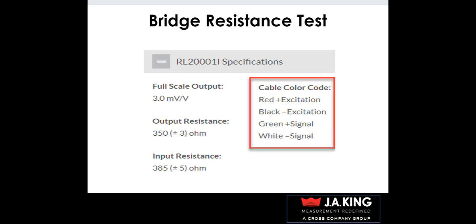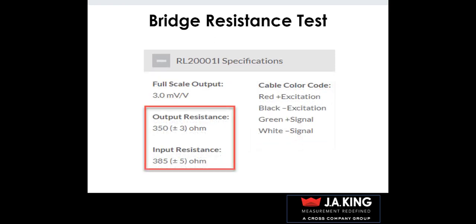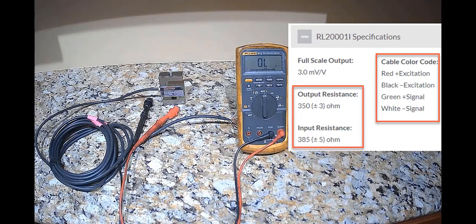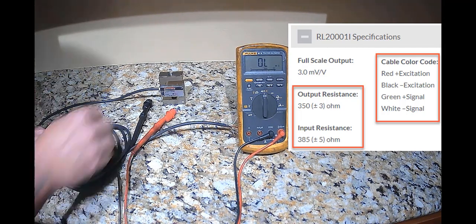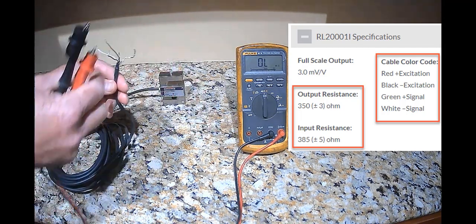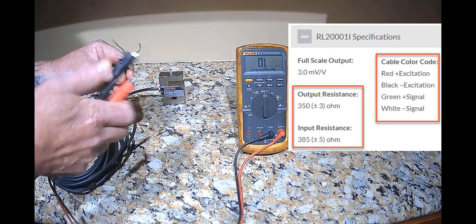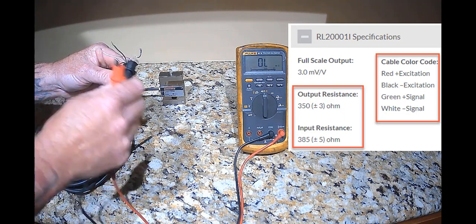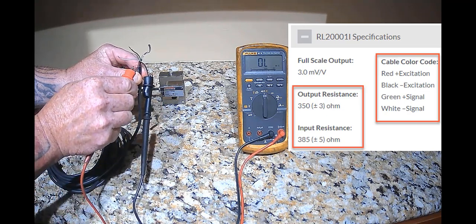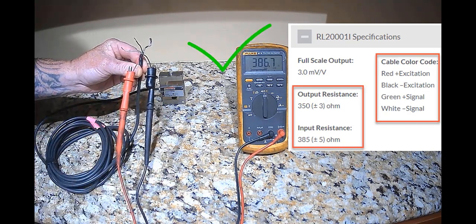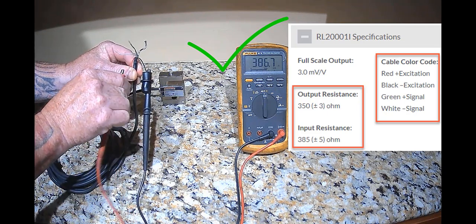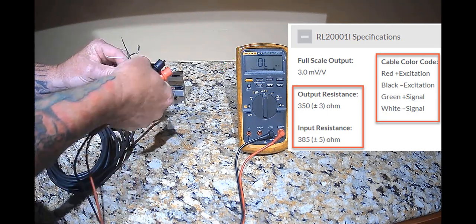Before testing bridge resistance, disconnect the load cell. Find your spec sheet and look for the color code and the output and input resistance specs. Find the positive and negative excitation leads and measure across them with a multimeter to find the input resistance. If the input resistance check is within specs, test the output resistance across the positive and negative signal leads.